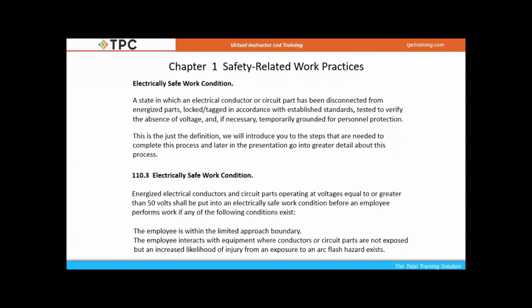OSHA says we have to have a lockout tagout procedure, but it's up to us to come up with our own procedure that's going to work at our facility. And then we have to test it to verify the absence of voltage. And we're going to go through an actual test today. I'm going to bring up a simulator that we will use. And if there is the possibility of the circuit becoming re-energized because of capacitance or induction, then we do have to put on ground straps. So that's just the definition, right? But we are going to see these steps coming up.